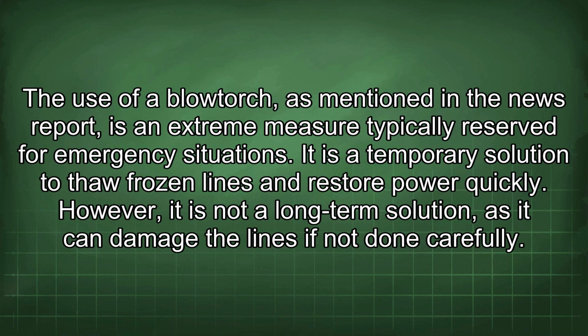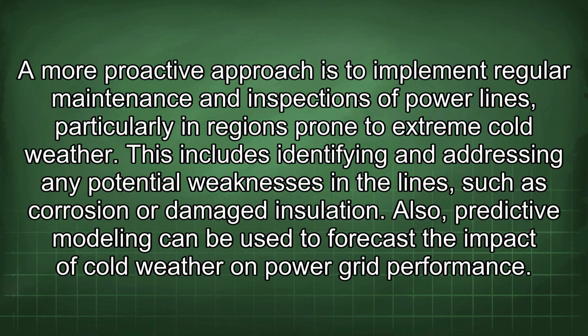The use of a blowtorch, as mentioned in the news report, is an extreme measure typically reserved for emergency situations. It is a temporary solution to thaw frozen lines and restore power quickly. However, it is not a long-term solution, as it can damage the lines if not done carefully. A more proactive approach is to implement regular maintenance and inspections of power lines, particularly in regions prone to extreme cold weather. This includes identifying and addressing any potential weaknesses in the lines, such as corrosion or damaged insulation.